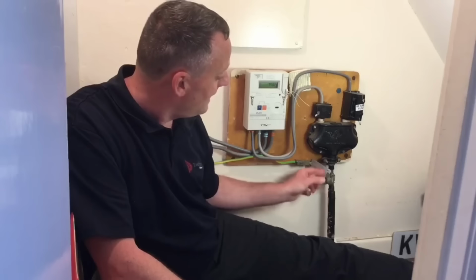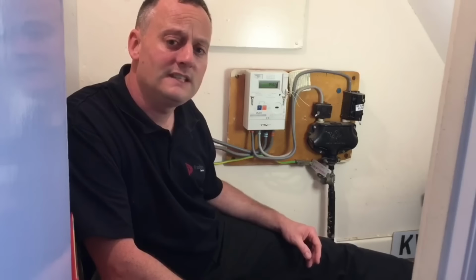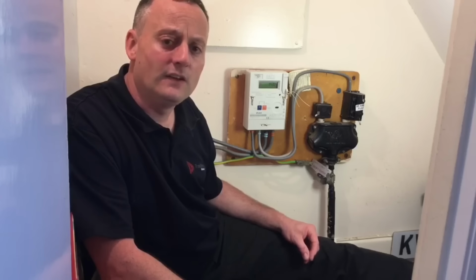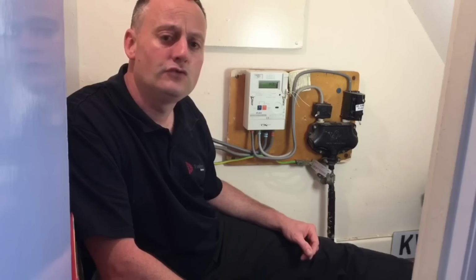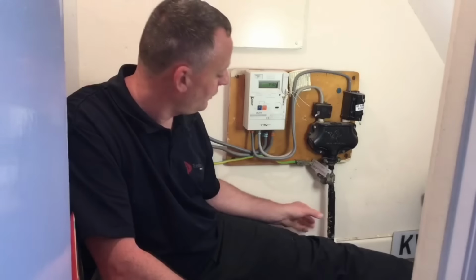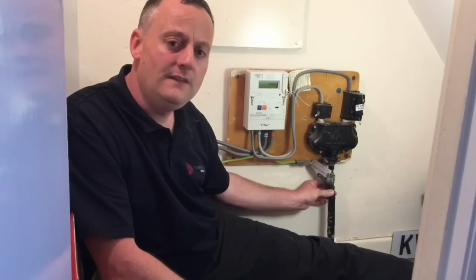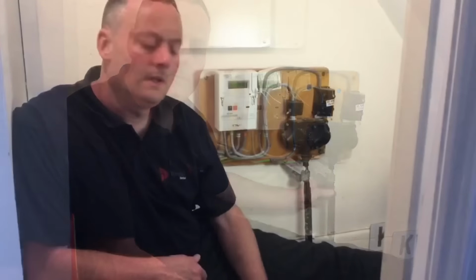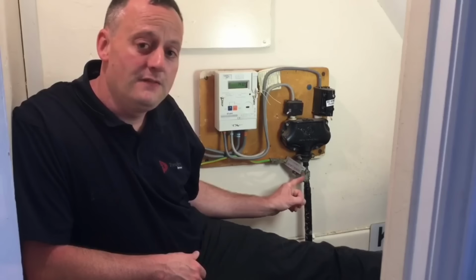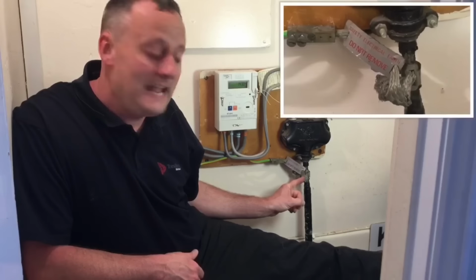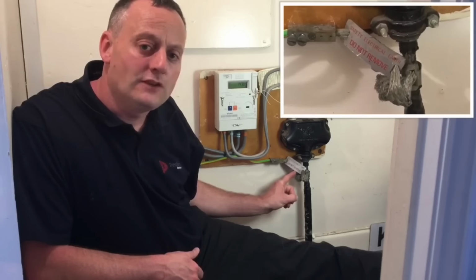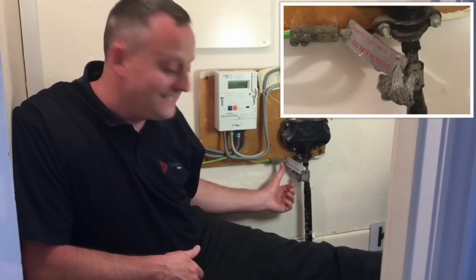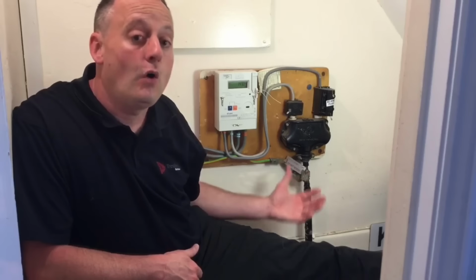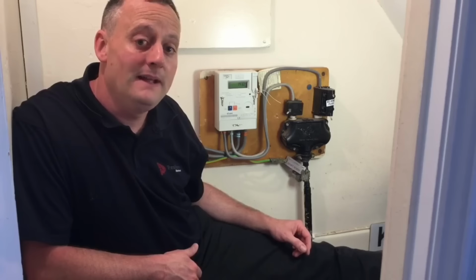We haven't got it coming out of our cutout as we did on our TNCS earthing arrangement, where the earthing conductor and neutral were together within the cutout. We've actually got it separated off the sheath of the incoming supply cable. We see the connection from the sheath of the incoming supply cable has been labelled with safety electrical connection, do not remove. If this was to be disconnected from the installation, the whole installation would lose its incoming earth.